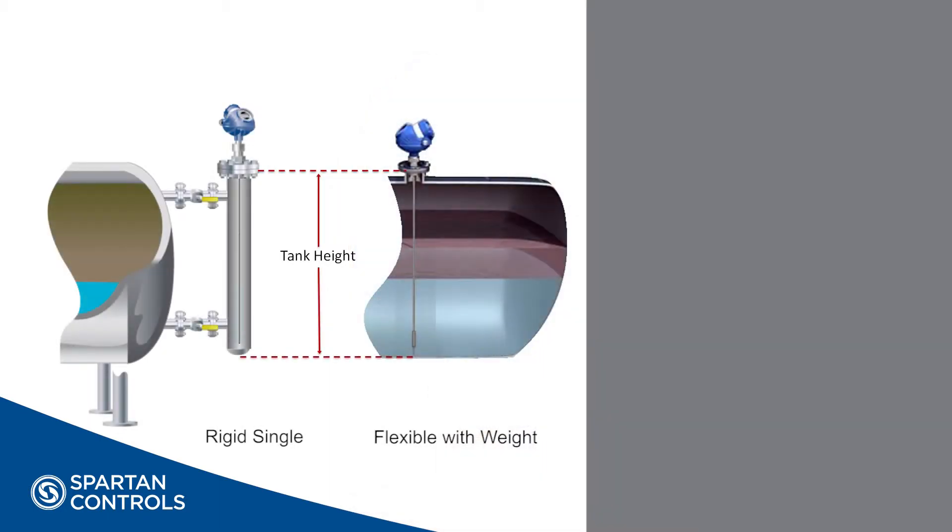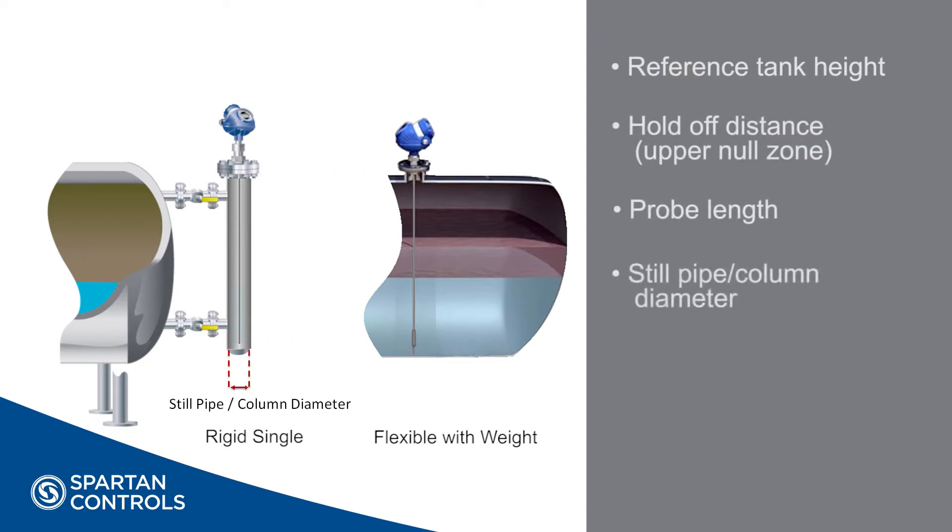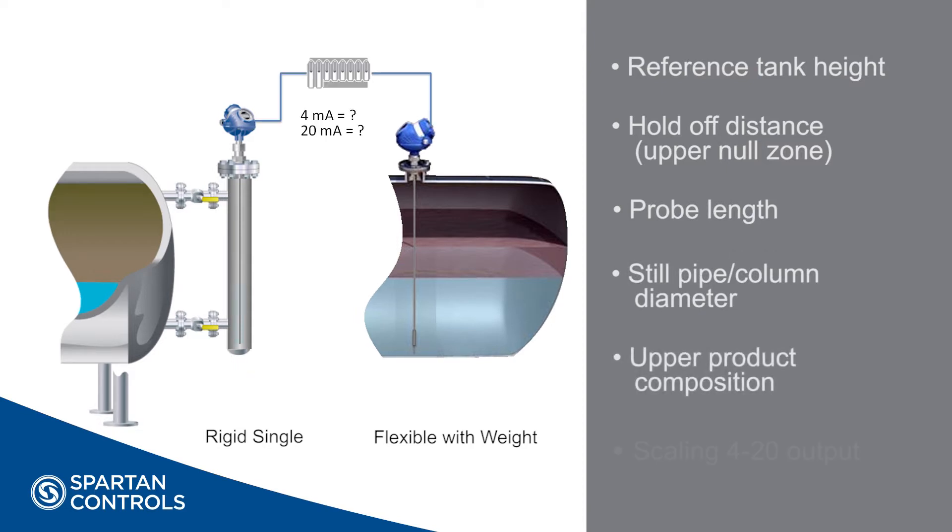Before configuration can begin, it's important to gather the following information: reference tank height, hold off distance, probe length, still pipe or column diameter, upper product composition if measuring interface, and scaling for your 4 to 20 output to the host.